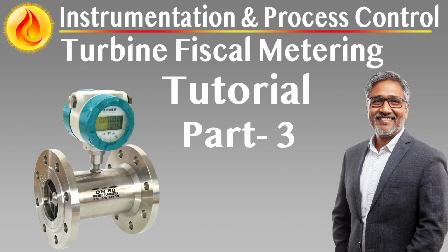Drainage and flushing provisions must be included to clean the sampler between batches, ensuring that each collection cycle is free from contamination or residue from previous samples. System reliability, timing precision, and accurate flow synchronization are critical, as the composite sample often forms the official reference for contractual custody transfer and product quality reporting. Sampling systems must therefore be integrated tightly with flow computation logic and alarm systems, with manual override and validation functions available through the station interface.